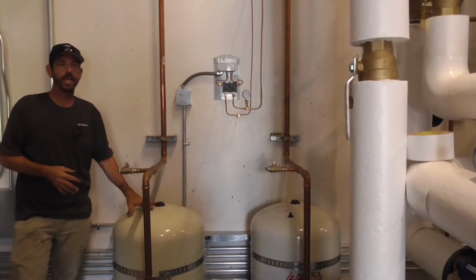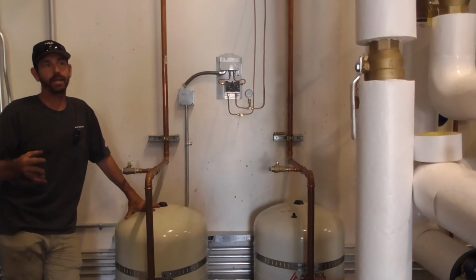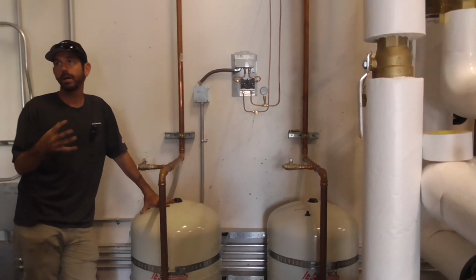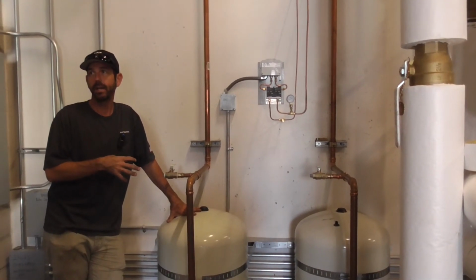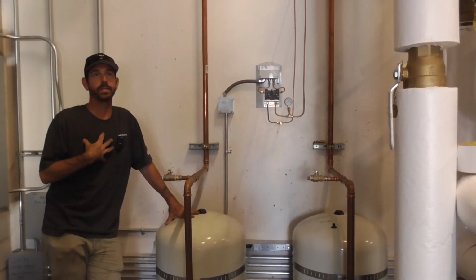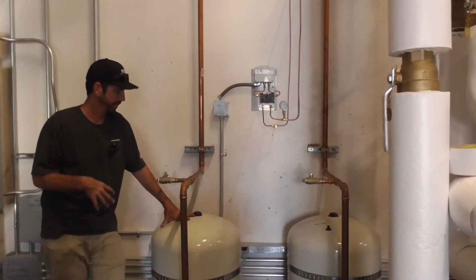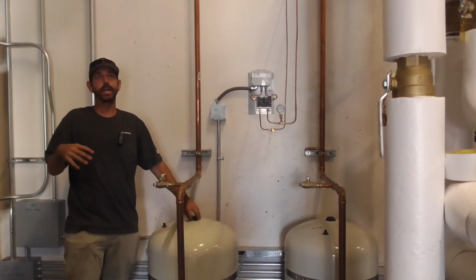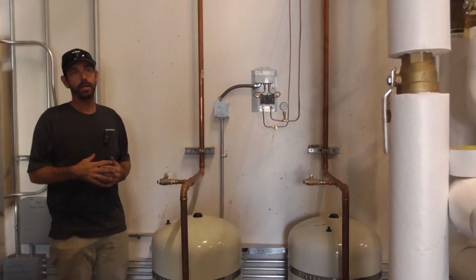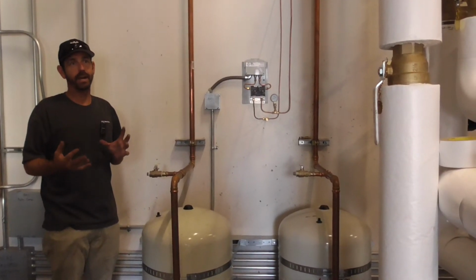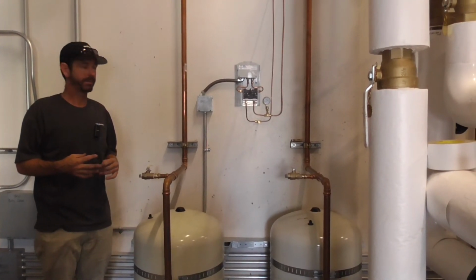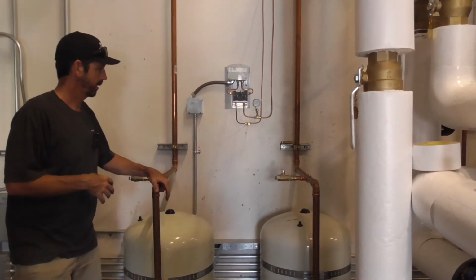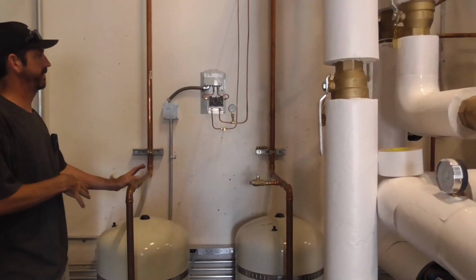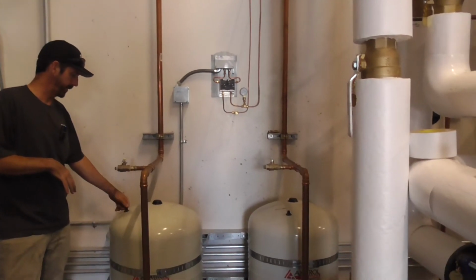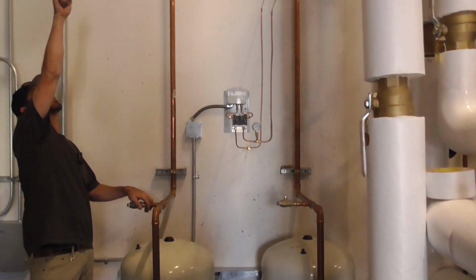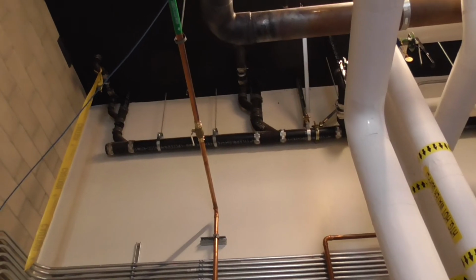When we charge these tanks, if you somehow have an air dryer system attached to an air compressor, you could use that. Dry air, we use nitrogen. It's easier for us to use nitrogen, so we want to charge these with nitrogen. It's an inert gas. It doesn't change pressure as easily as air does, depending on its temperature. Those are the two expansion tanks and what they're for. Once you're done checking your set point, put the cap on, close this valve, and then you can slowly open your shut-off valve.